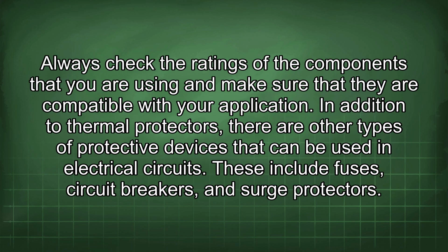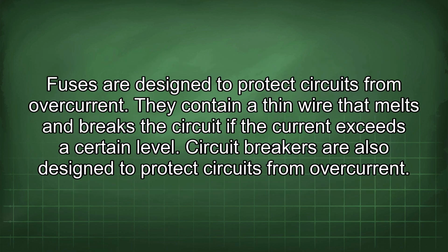Always check the ratings of the components that you are using and make sure that they are compatible with your application. In addition to thermal protectors, there are other types of protective devices that can be used in electrical circuits. These include fuses, circuit breakers, and surge protectors. Fuses are designed to protect circuits from overcurrent. They contain a thin wire that melts and breaks the circuit if the current exceeds a certain level.